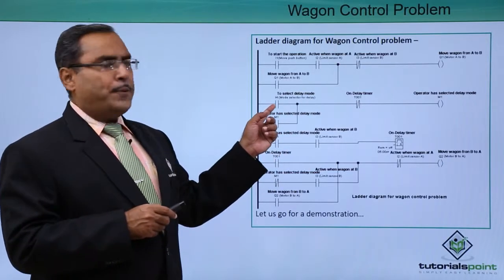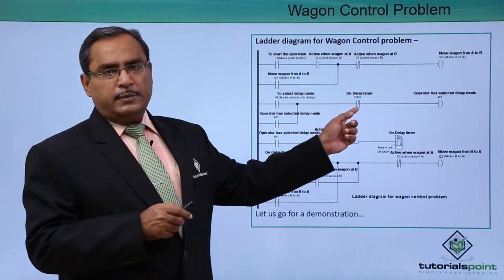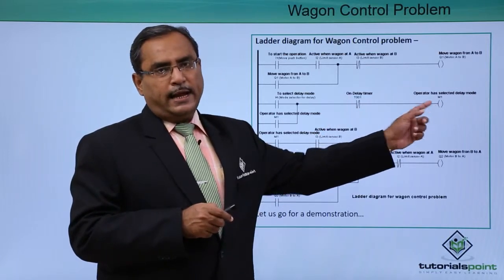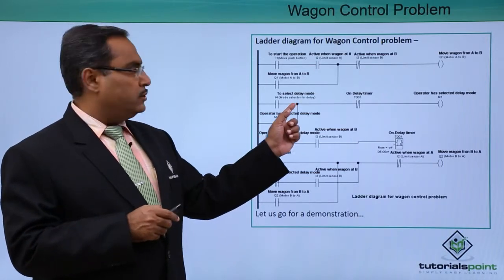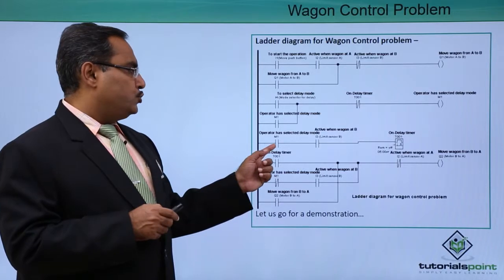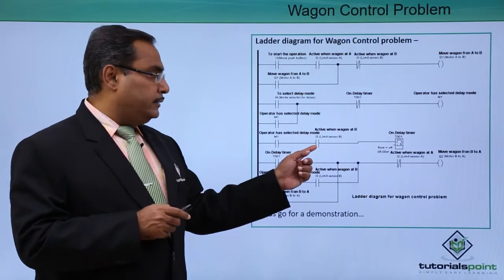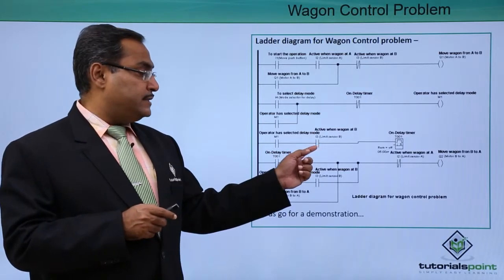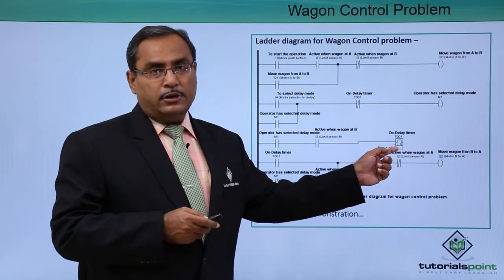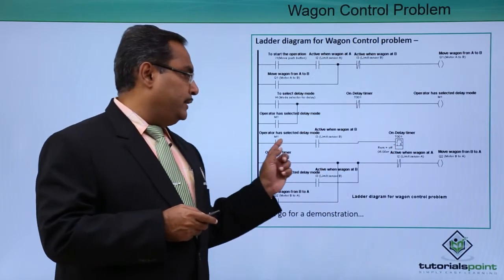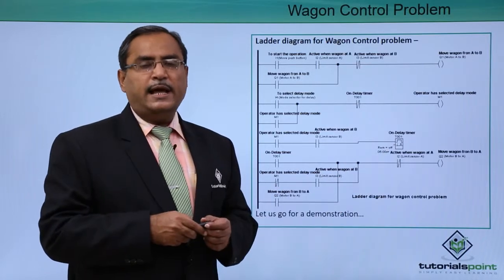The next rung handles the delay mode. When the operator selects the delay switch, M1 indicates the delay mode has been selected. A latch is provided since the input is a push button. When M1 is on (delay mode selected) and the wagon is at station B, the on-delay timer activates. The timer parameter is set to 5 seconds.